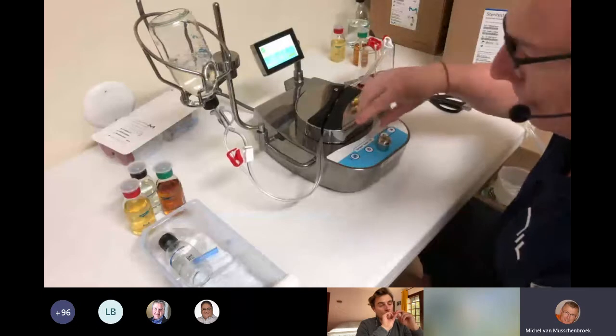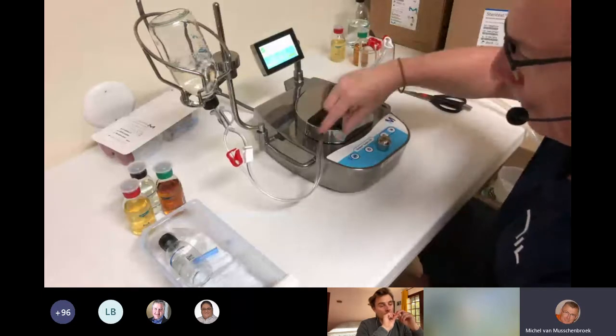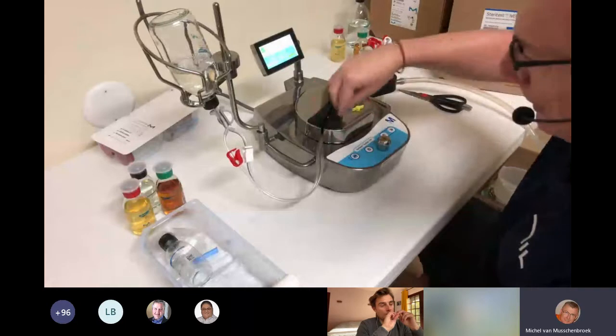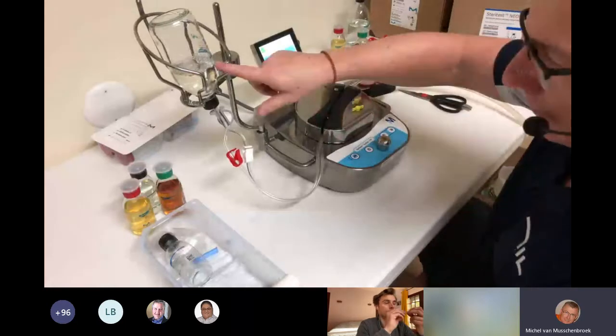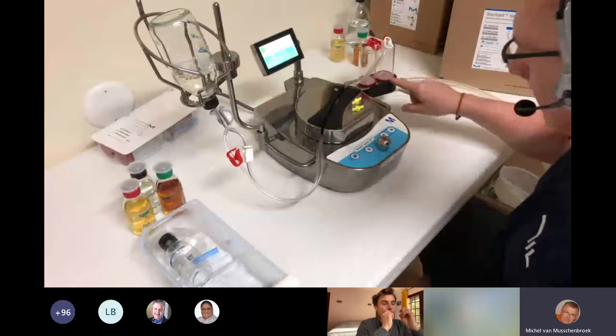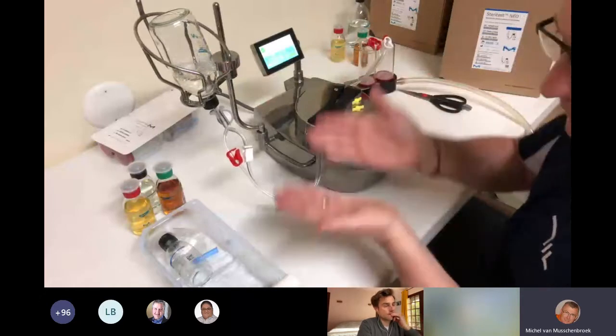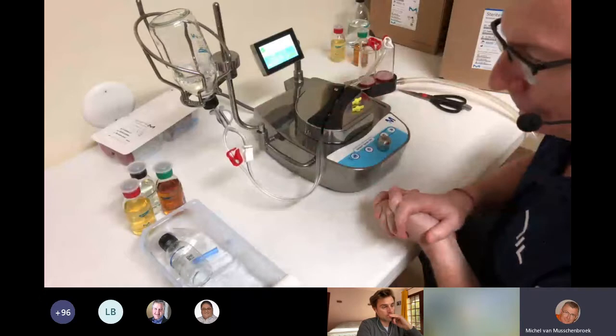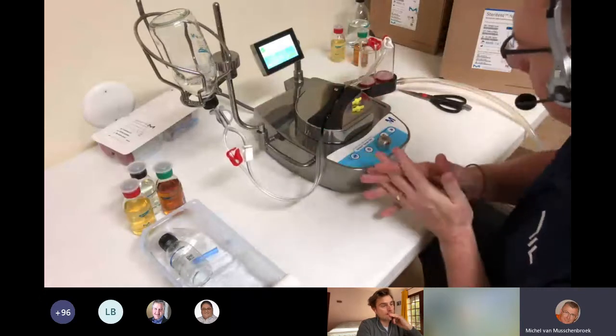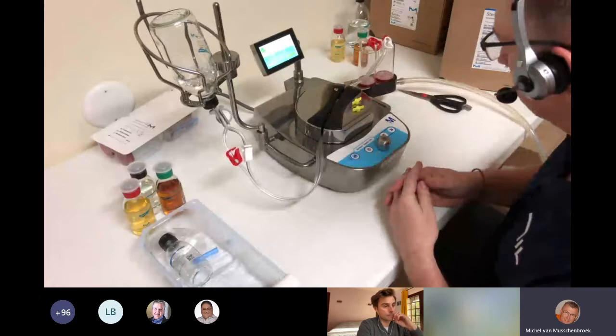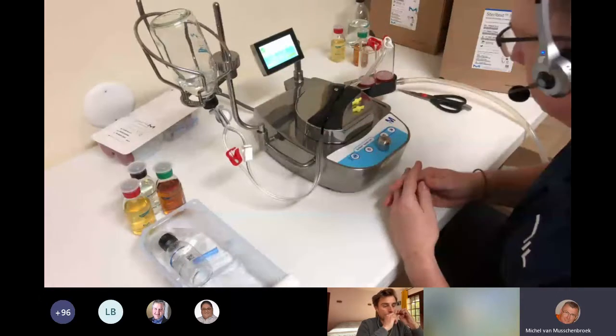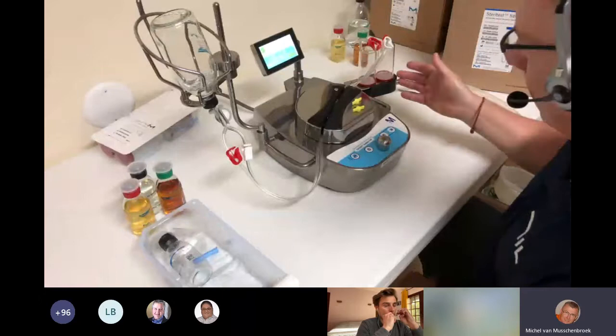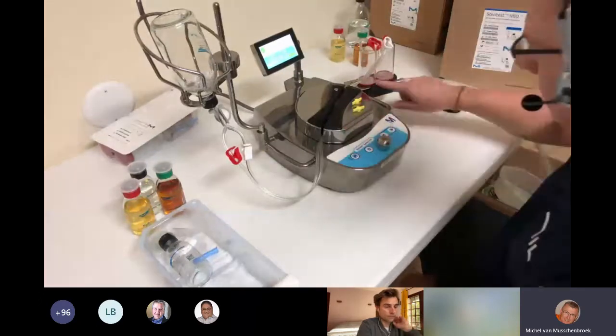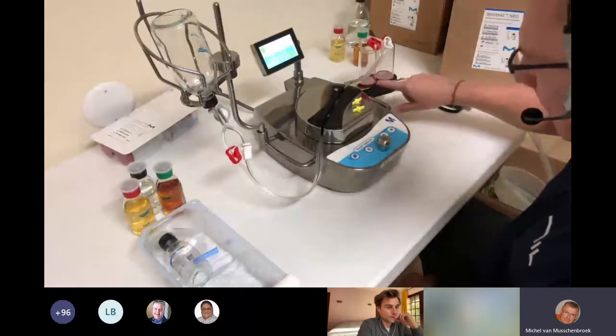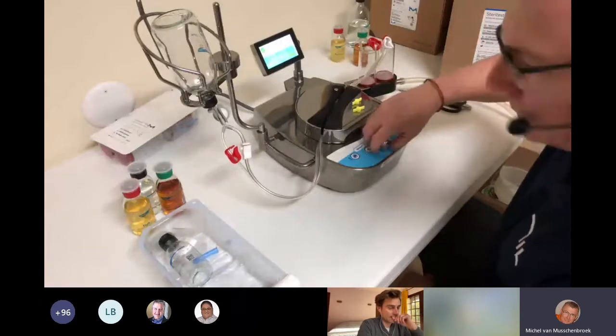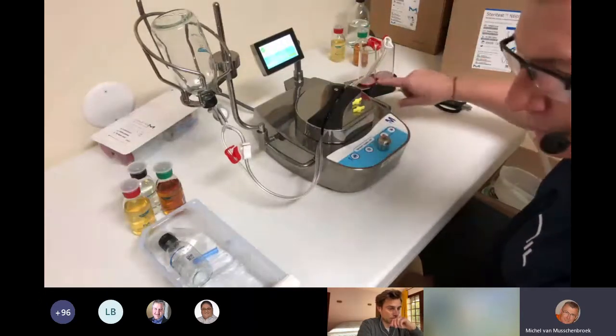During that service, they ensure the pump is operating correctly so that the product being run through on both sides is equal, and you're not getting a wide variety here. The pump speed can be modulated through here. When you're performing your test, you can see I'm not getting any bumps or bubbles. You don't want the speed to go up so high that you're getting bubbles through your unit.